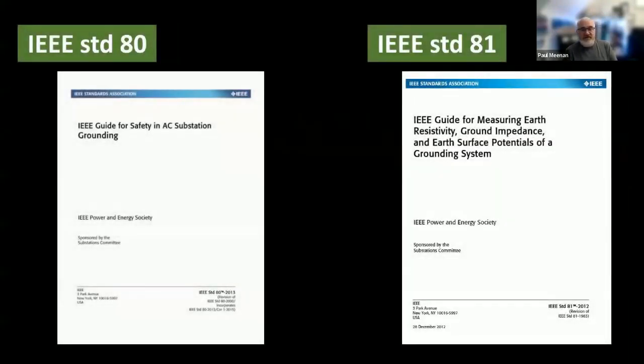If you wanted to look further afield, there is IEEE Standard 80 in America and parts of America, which is a guide for safety in substation grounding. Grounding is very similar to earthing. There is also the IEEE guide for measuring earth resistivity. These are some very good standards. Standard 81 from the IEEE, if you want to further research the subject, if you're writing your own papers about the effects of energy dissipation and good earthing or bad earthing.